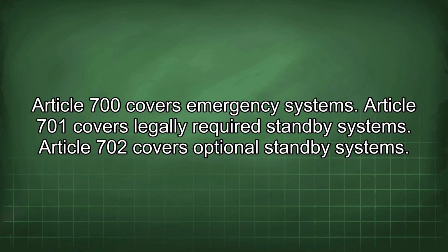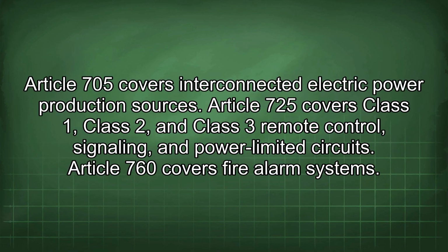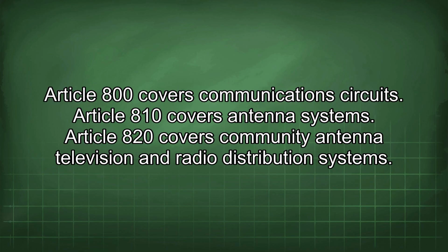Article 701 covers legally required standby systems. Article 702 covers optional standby systems. Article 705 covers interconnected electric power production sources. Article 725 covers Class 1, Class 2, and Class 3 remote control, signaling, and power-limited circuits. Article 760 covers fire alarm systems. Article 800 covers communication circuits.